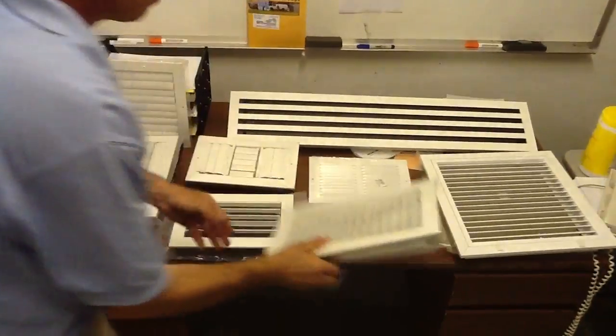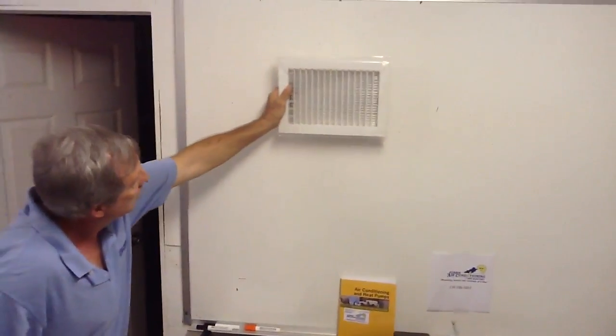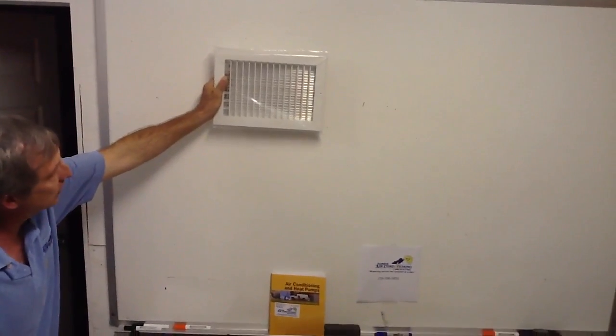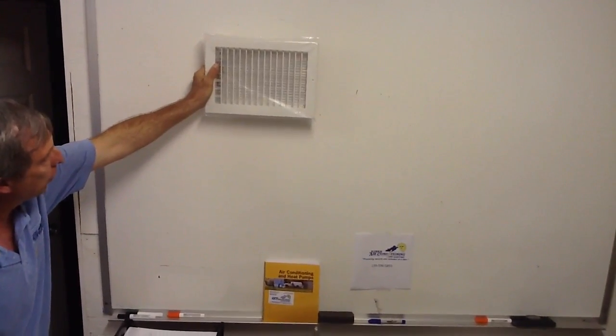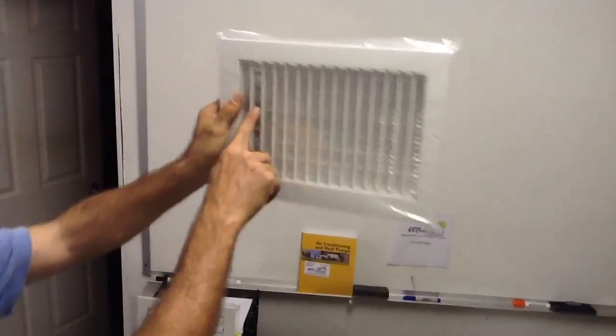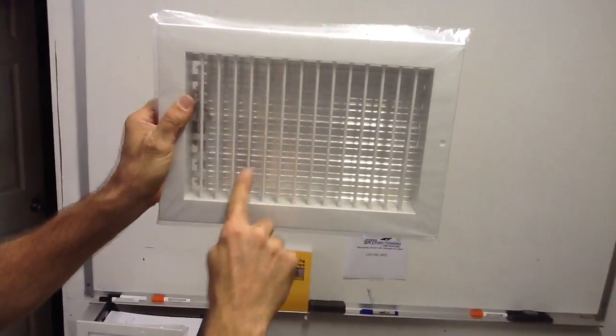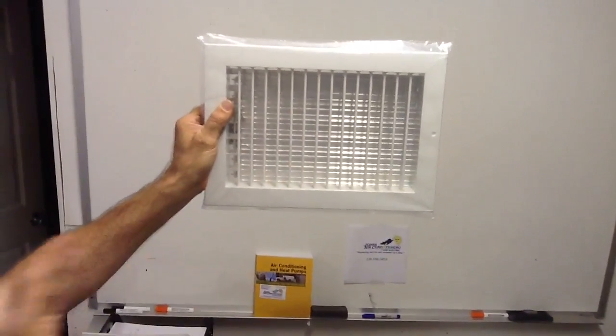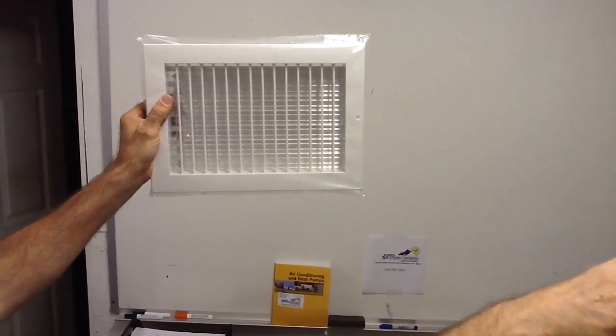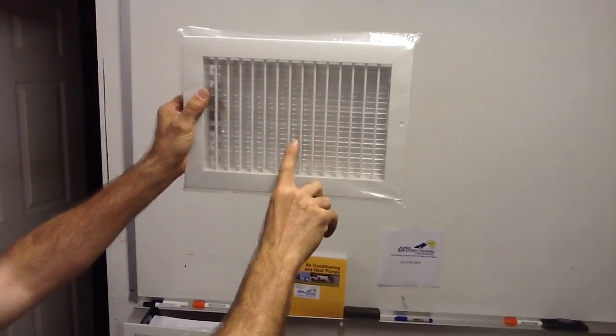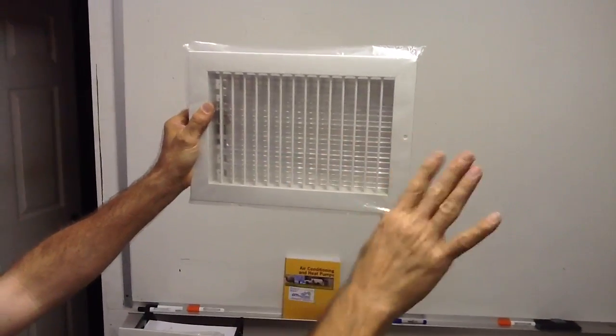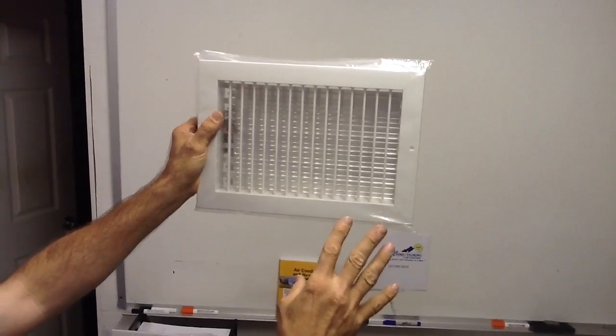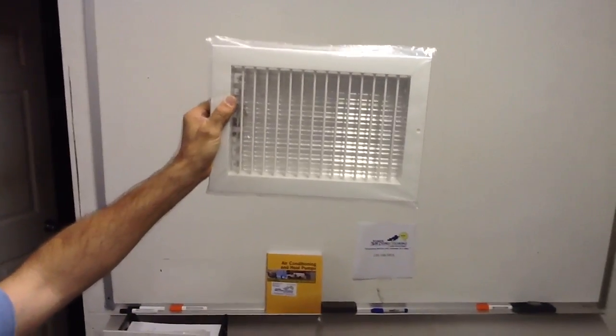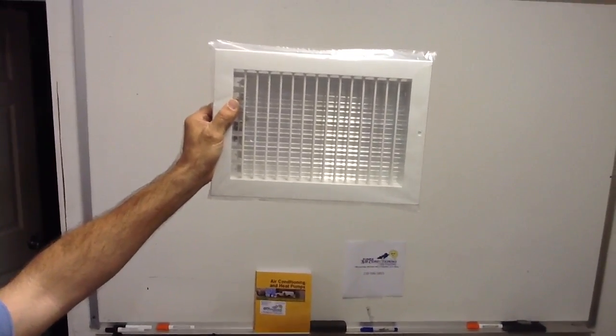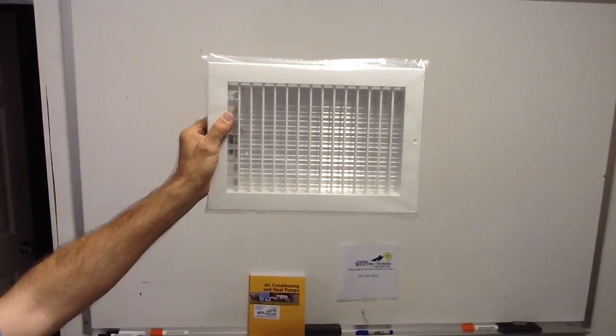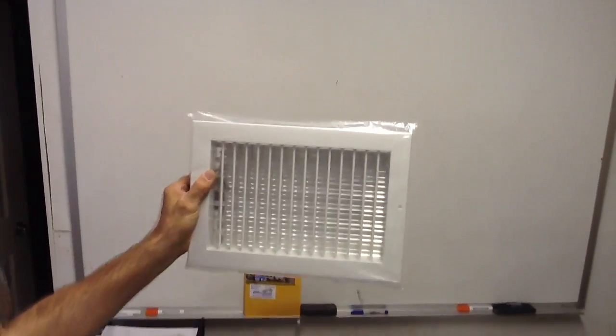Here is a sidewall grill. Sidewall grill says what it is. It goes in the sidewall. You see the wide diffusers are more than a half inch wide. So as the air blasts out, you have a great throw, a distance, where this particular grill will blow out about 10 to 12 feet. Depending on the velocity of the airflow coming out, this thing could work great in rooms where you have very little ceiling height, or you have a knee wall, or somewhere you just can't get the ductwork and you have to put it in a sidewall.